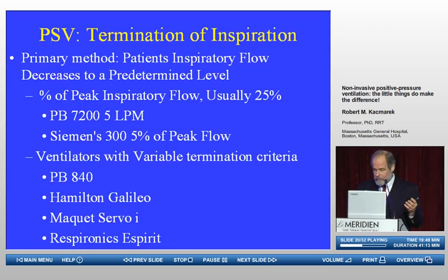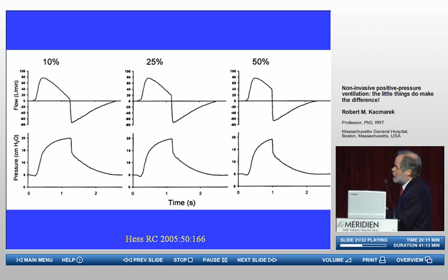And if we simply look at this depiction, this is what is essentially happening. If we set that termination criterion at 10%, that means that when the flow drops to 10% of that maximum level, the breath will end. If I set it at 25%, when it drops to 25% of the maximum level, the breath will end. Or at 50% of the maximum level. So if the patient chooses, as many stressed patients do, to end the breath while inspiratory flow is still very high, with this option we should be able to adjust in order to allow the ventilator to coincide ending the breath with the patient's desire to end the breath. Now, of course, this requires you to be observant, pay attention, and readjust this.